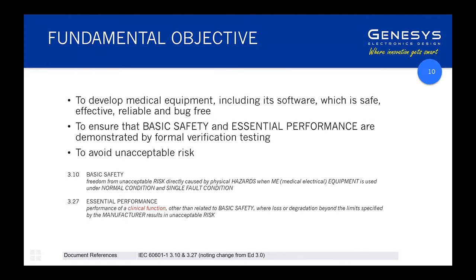The other key concept is essential performance — effectively everything other than basic safety that is required for the device to be safe and effective in performing its function. Defining the essential performance of your device is a key aspect of the standard. A fairly good view is: what does this device have to do to fulfill its clinical function, be that therapeutic, diagnostic, or otherwise? Throughout the presentation there are references to documents you should be producing during development.